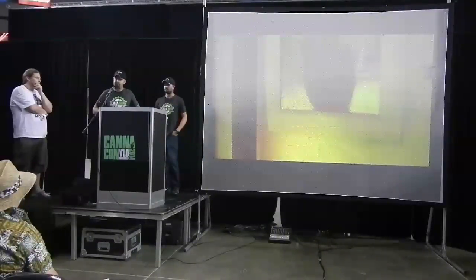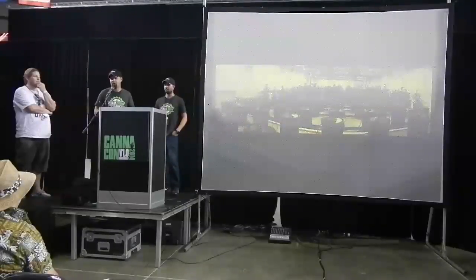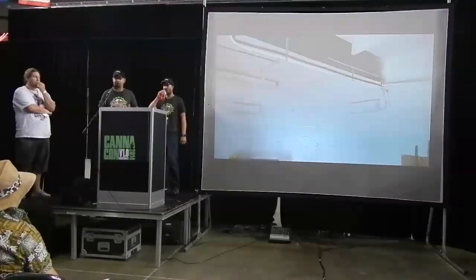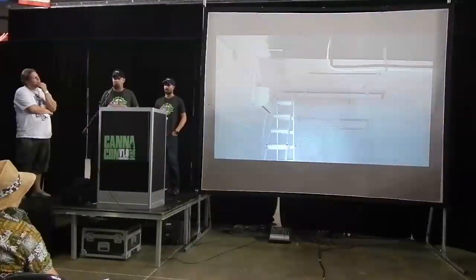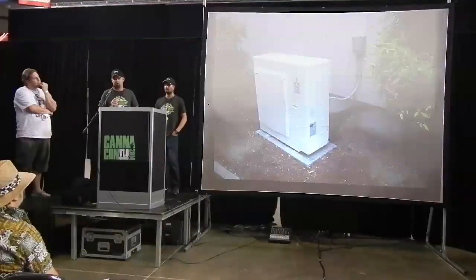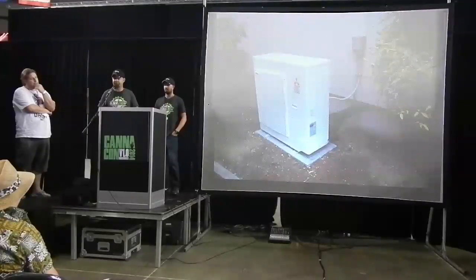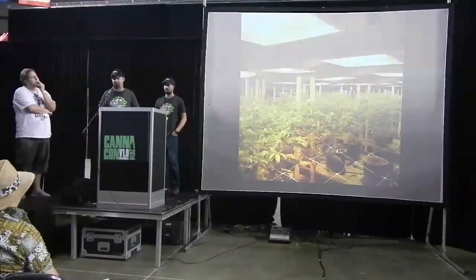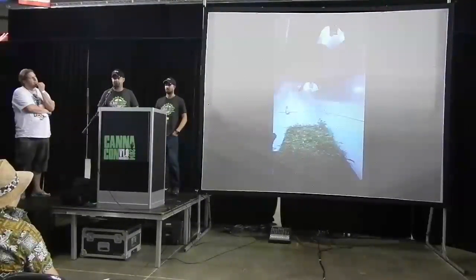You add moisture and live plants, something giving off heat and moisture constantly, and it'll go up a lot more. Unfortunately, we've seen emergency cases where the AC goes down and they call us up, and they're not monitoring their room to make sure the climate control stays in spec. For example, last week we got a call from a smaller medical operation. For 12 hours his monitoring system went down and he was not regulating it. A little 30 amp fuse popped on the AC system. His room went up over 130 degrees and 99% humidity, and he did lose his crop. That's the first time we've ever seen someone lose their crop. Typically, they'll catch it within an hour or two and start turning their lights off to save themselves.